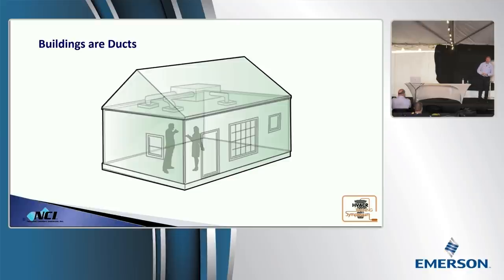You're going to like the end of this, because we're going to talk about how to fix that, depending on your installation. And all these people that are putting these big kitchen things in anymore. You know, they went from a standard fan, and they put it in, this thing's taking 600 or 700 CFM out. Well, then it's got to get that air from somewhere. That's right. And then you will start pulling down the combustion. Excellent. So the comment was made on combustion air. We're putting 600, 700, sometimes up to 1600 CFM exhaust hoods in residential appliances. That air has to come back in from somewhere.